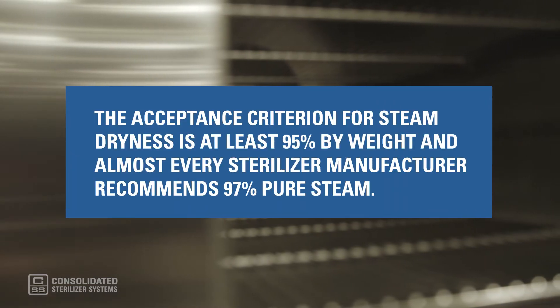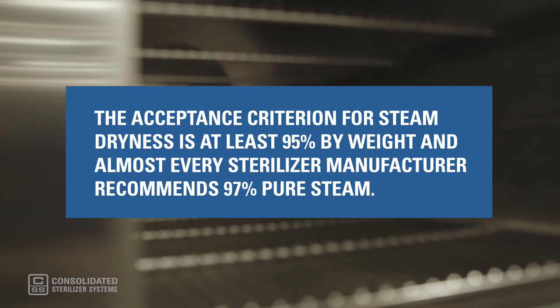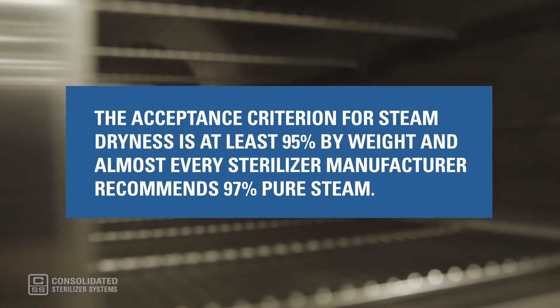Steam dryness is calculated by measuring the temperature change in a known amount of water in relation to the mass of steam that is required to cause that temperature change. Because the dryness value of the steam at the chamber entry point can be a bit lower than the dryness value in the sterilizer, measurements of steam dryness should be made at both locations. The acceptance criterion for steam dryness is at least 95 percent by weight, and almost every sterilizer manufacturer recommends 97 percent pure steam. In reality, a dryness level as low as 90 percent is considered acceptable for laboratory autoclaves. Steam dryness values below 90 percent, however, are considered to be wet steam, which does not deliver as much energy to the load.